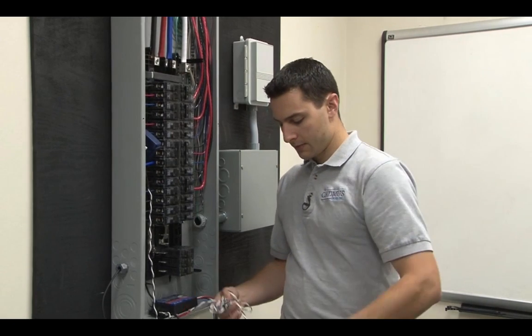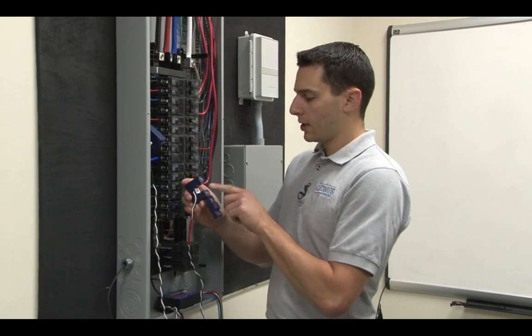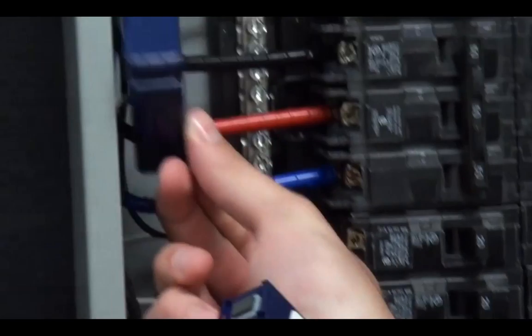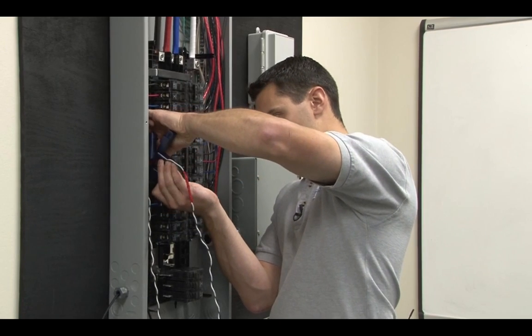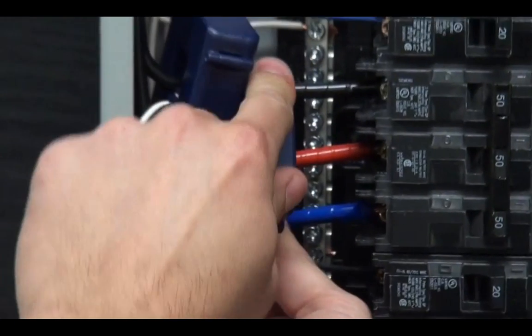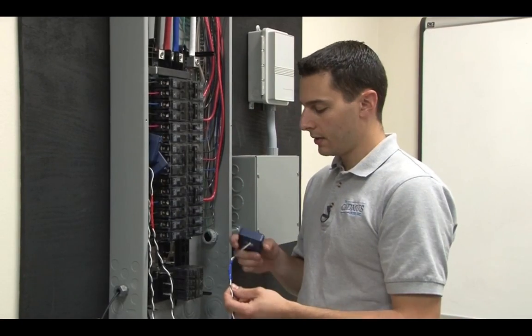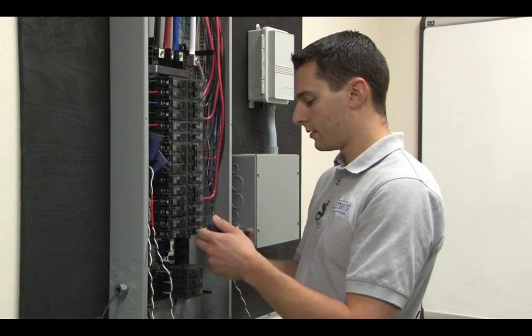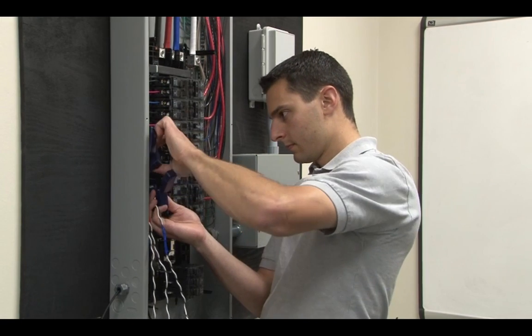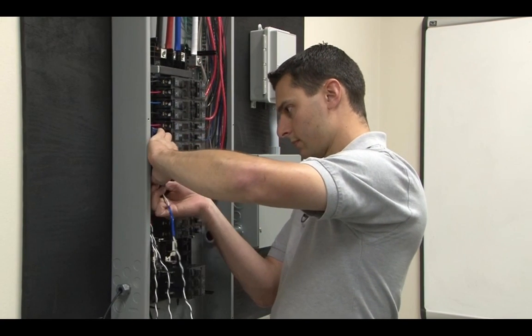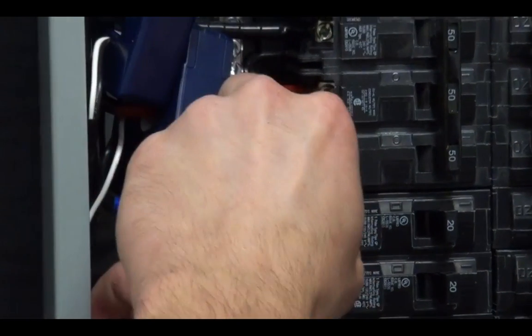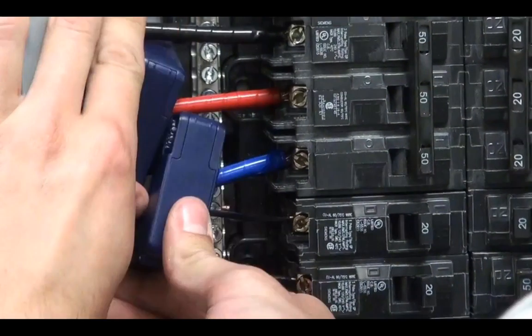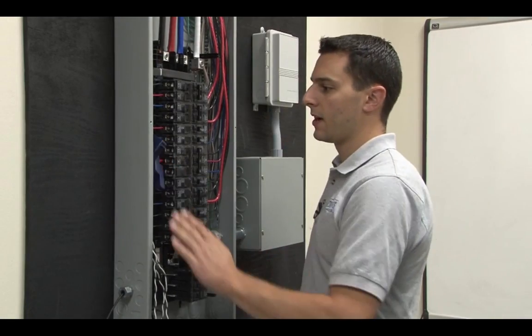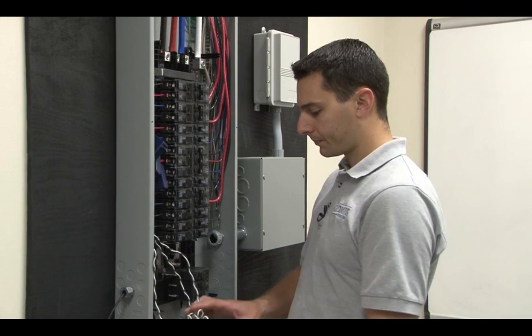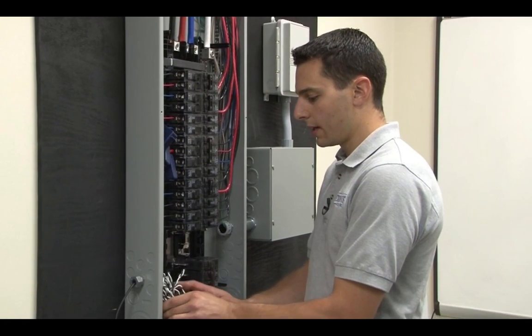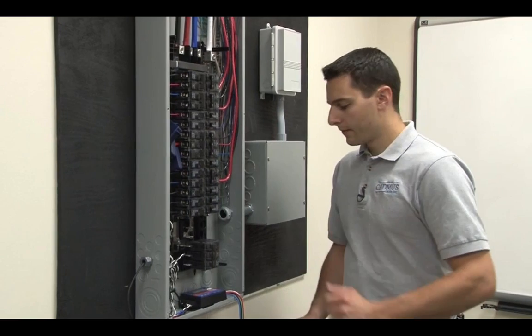We'll now move on to the red, phase B. Make sure the arrow faces the source, and this will go around the red conductor of our circuit. And lastly, our blue CT, phase C, will go around the blue conductor. We'll want to tuck the CTs in deep enough to allow for the enclosure cover to be installed. We'll neaten our CT wires, and then we can move on to our voltage leads.